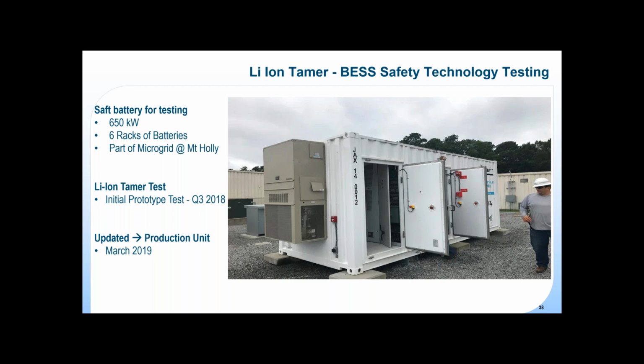That's why you test, you go to the field, and that's why our Mount Holly site was created, to understand what we were up against in deploying these new technologies. So we installed that initial prototype test in Q3 of 2018. It was functional, but those 6 sensors installed on 6 racks of batteries, plus another sensor for the HVAC, took us about a day and a half to install.